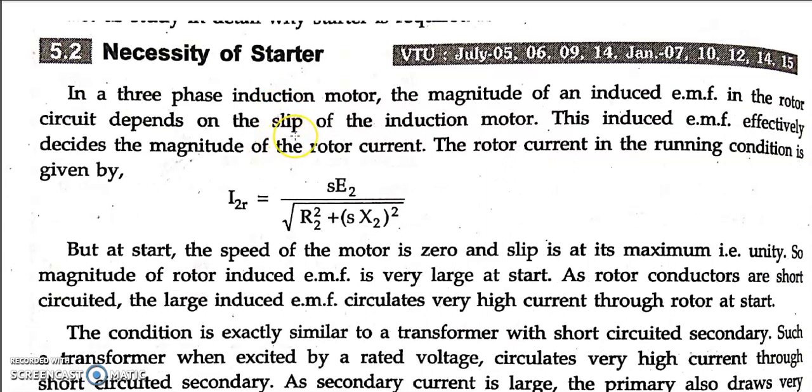You should remember that while starting a motor from standstill condition, that is speed is 0, what happens when you turn it on? It draws a huge current, around 5 to 8 times the rated current. Say if the rated current is around 5 ampere, it would be around 40 ampere. So initially it draws around 40 ampere for a few moments, or a few seconds.